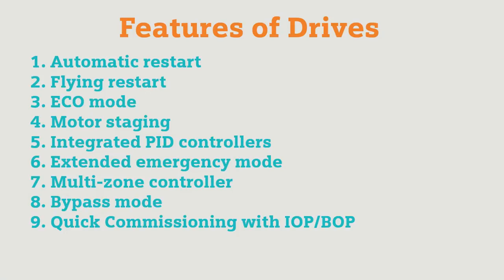Extended emergency mode can be activated in the event of fire. Multi-zone controller is also used in the closed-loop control system. Bypass mode: when there is a setpoint change or a fault, changeover to line operation can be done with this bypass mode. We can also make quick commissioning with the intelligence operating panel or basic operating panel — in short time we can commission this drive.